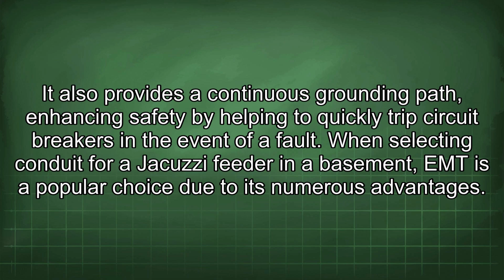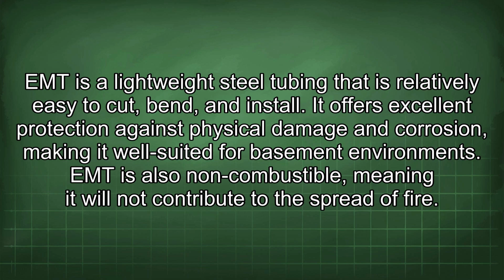When selecting conduit for a jacuzzi feeder in a basement, EMT is a popular choice due to its numerous advantages. EMT is a lightweight steel tubing that is relatively easy to cut, bend, and install. It offers excellent protection against physical damage and corrosion, making it well suited for basement environments. EMT is also non-combustible, meaning it will not contribute to the spread of fire.